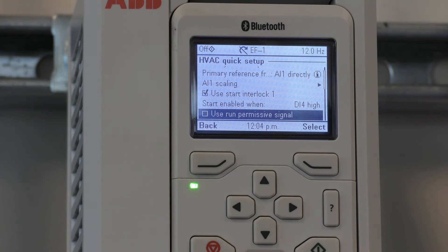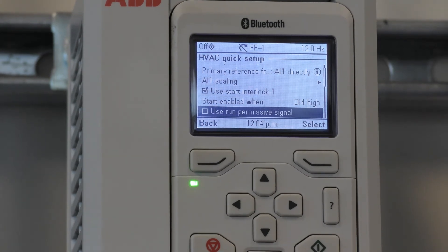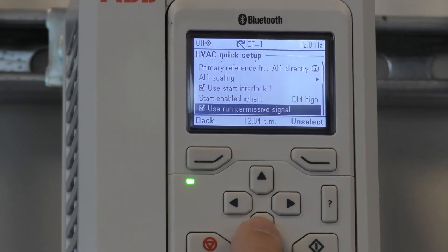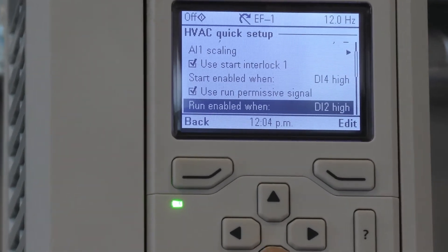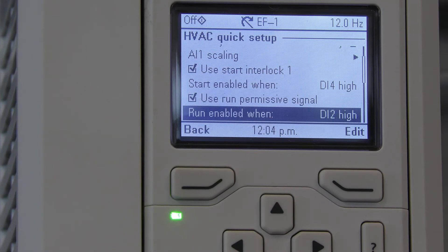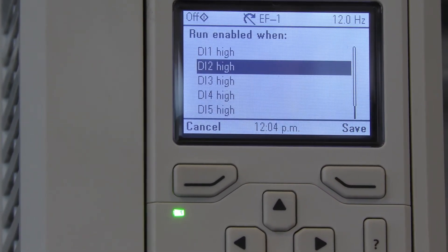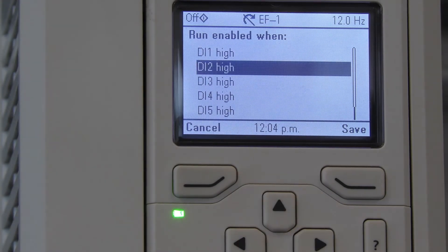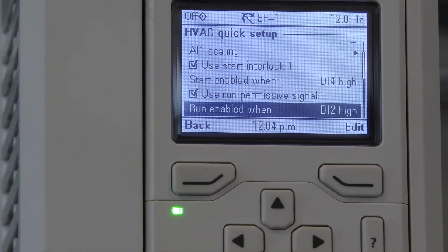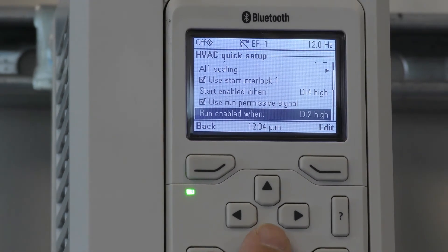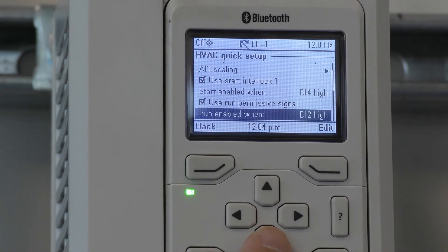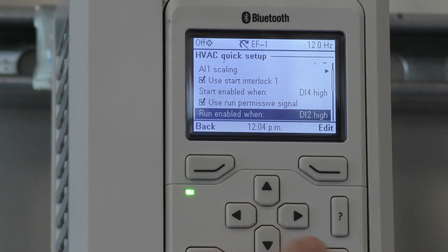This is where you can select a run permissive signal. If you select this, it allows the drive to use a run enable when digital input 2 is high. You can edit this to other digital inputs. This would typically be used for a damper end switch or an output contactor with an aux relay that would tell the drive that the contact is closed and allow it to operate at the appropriate time.